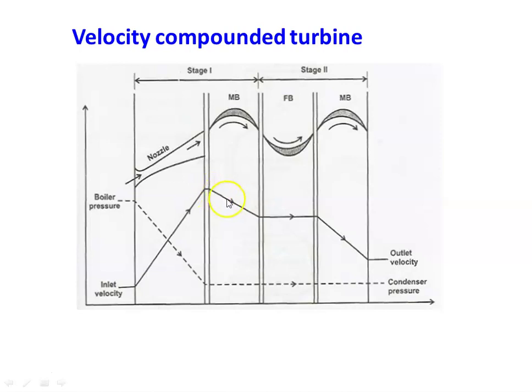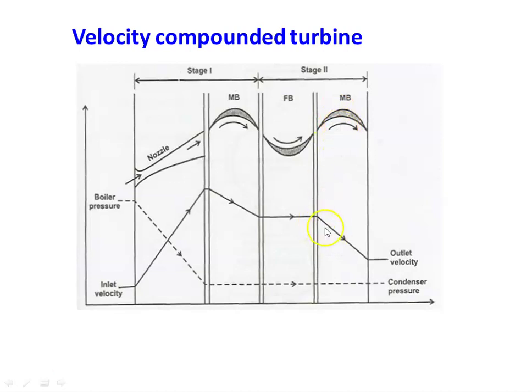In the first moving blade there is a certain percentage of decrease in velocity, and this decrease in velocity is converted into work. The velocity then remains constant in the fixed blade. The fixed blade is attached to the casing of the machine; its purpose is to deflect the steam to the next moving blade without loss of velocity or pressure. In the next moving blade, the velocity of the steam is utilized once again, and there is a further decrease in velocity as steam leaves.